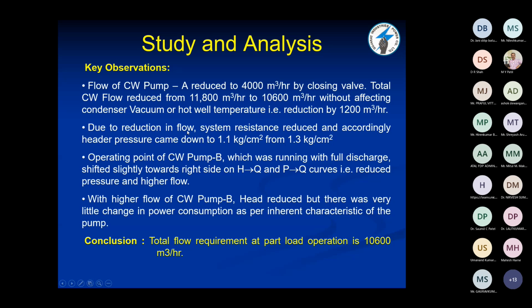Now, due to reduction in flow, system resistance reduces and corresponding header pressure came down to 1.1 kg from 1.3 kg. The operating point of cooling water pump B, which was running with full discharge, shifted slightly towards the right on the head-flow HQ curve and PQ curve. I will show those curves also. That is reduced pressure and higher flow. Now with higher flow of CW pump B the head reduced, but there was very little change in power consumption as per the inherent characteristics of that pump.